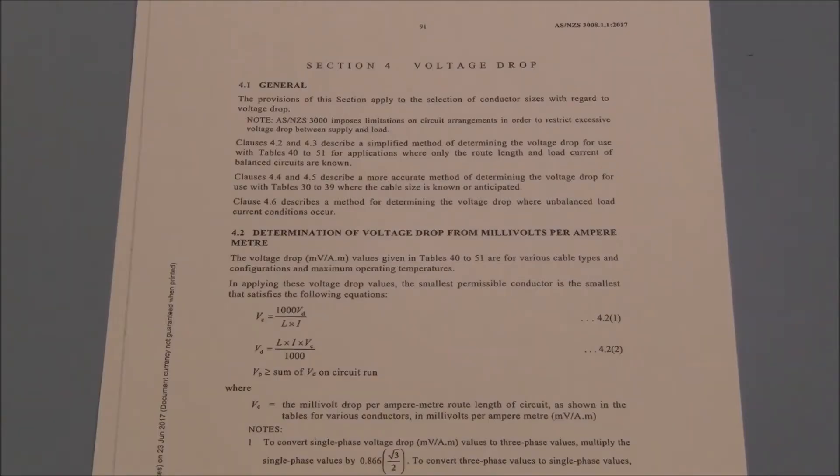Section 4 of AS3008 lists a number of methods relating to voltage drop. We will be concentrating on the millivolt per amp-metre method.